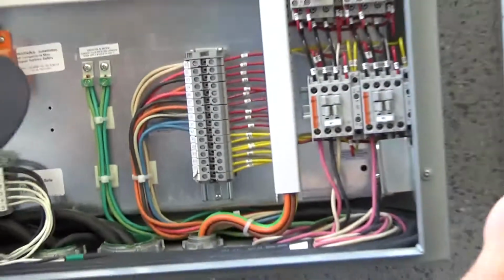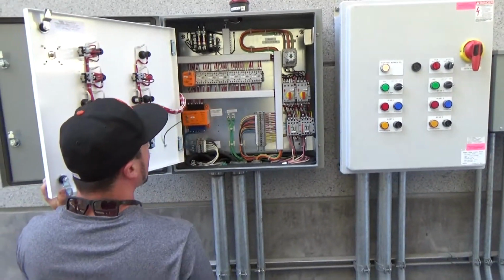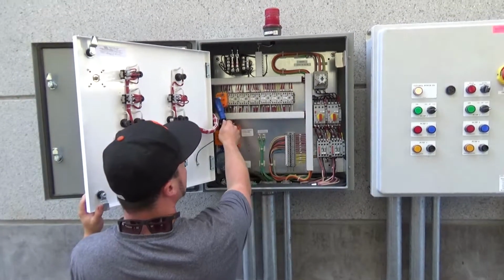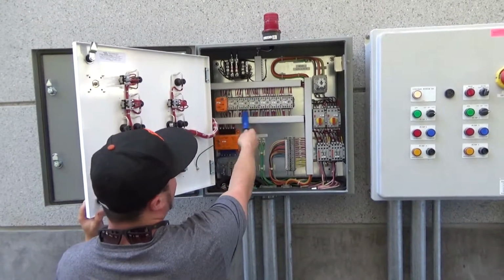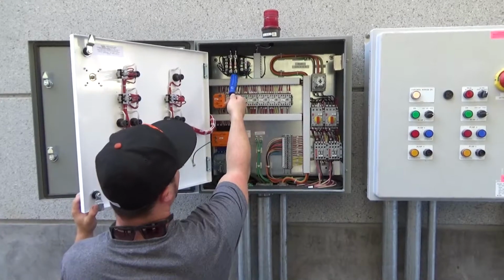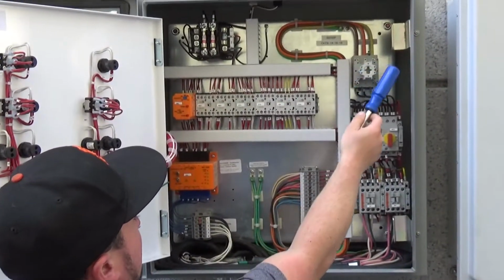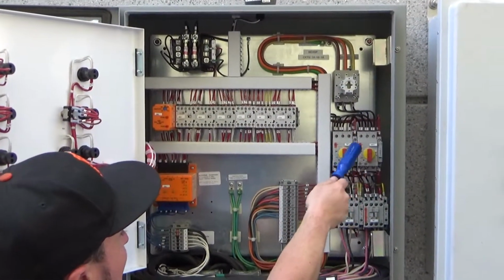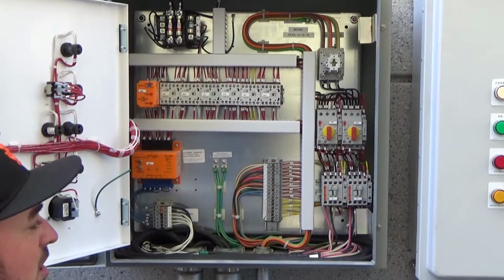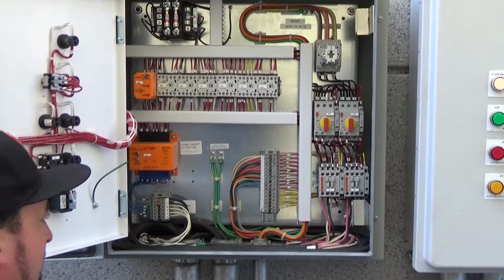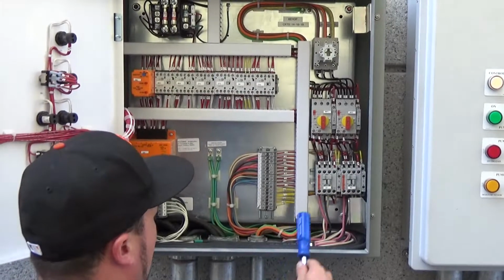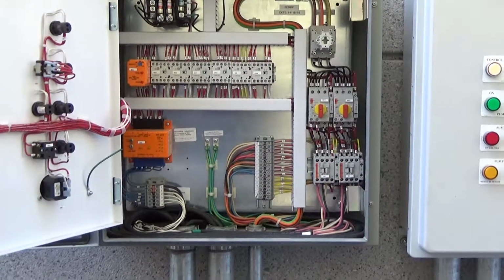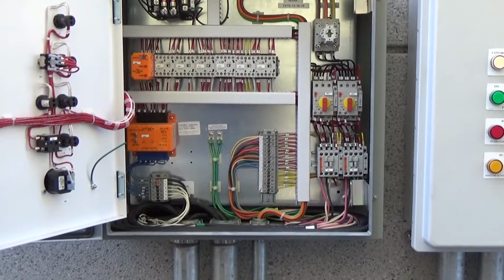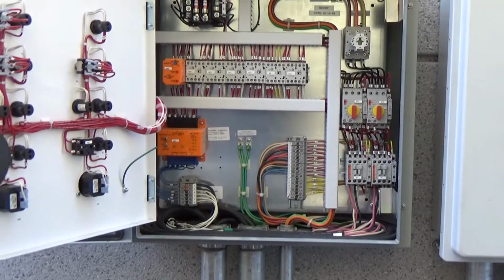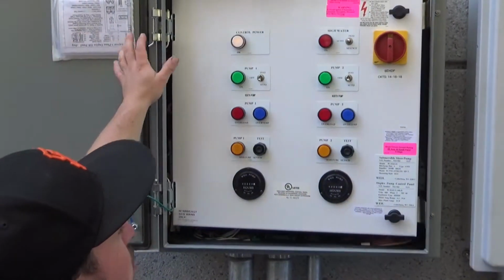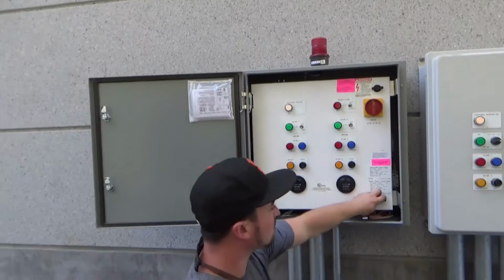This bad boy, like I said, does not have that. Inside the panel, this is in regards to the moisture sensor. You just have little devices in here: transformer, main disconnect, and you have your overloads right here for each pump, just like that other pressure booster panel. You have your starters, and each starter corresponds to a certain pump. Super basic. The wiring diagram is located right here for troubleshooting. If you guys ever have to troubleshoot, there you go.